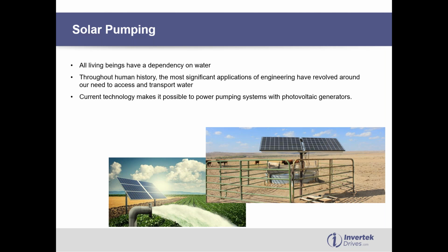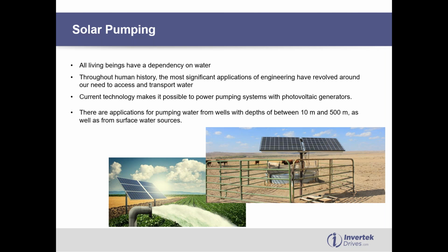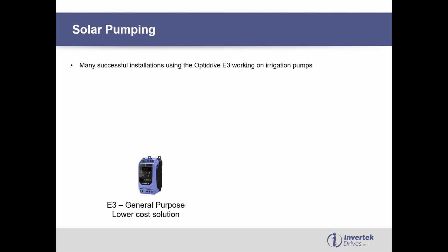So what we have now in the current technology is it makes it possible to power these pumping stations or pumps directly from photovoltaic generators, so solar panels. We do a lot of applications for pumping groundwater from quite deep wells, anything from 10 meters down to 500 meters, as well as surface water type applications. So anywhere remote where there's not an easy connection to the mains, the power grid, then we can use solar panels to supply power to the drives.